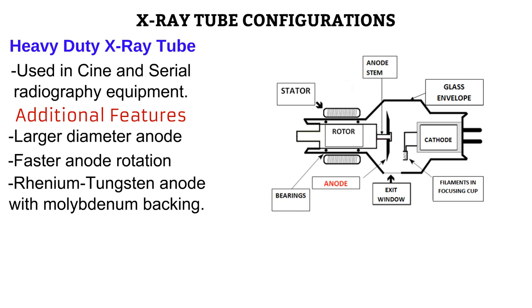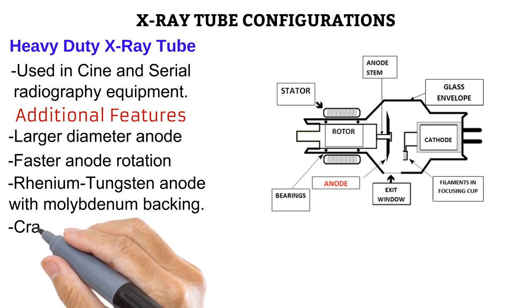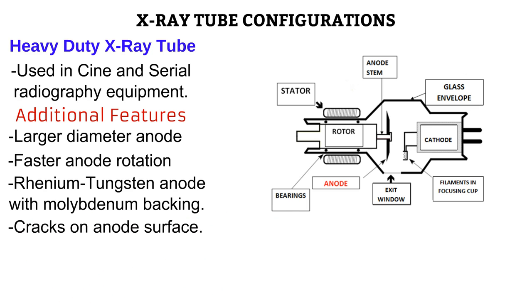Also, instead of just tungsten, as seen in the conventional X-ray tube, the heavy-duty anode is made more compound with an alloy of both tungsten and rhenium. It also has a backing that is made of either molybdenum or graphite. This compound anode gives it a greater thermal capacity, allowing it to store more heat than regular tubes. The anode also has certain cracks on its surface. These cracks are placed on purpose to give room for the anode to expand when hot and contract when cool without getting distorted.